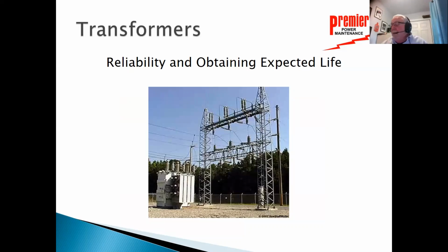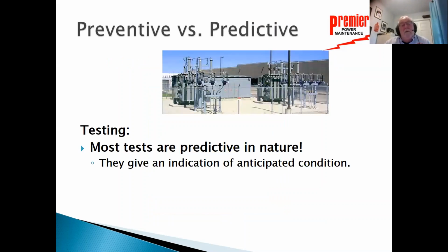So the second topic I want to talk about with regard to specific sections of reliability is the transformer. Let's talk about reliability and obtaining expected life out of a transformer. We get hired oftentimes to come out and the customer wants us to do preventive maintenance. Well, we need to discuss what the difference is between preventive maintenance and predictive maintenance. Almost all the tests that we do are predictive in nature. We're not preventing anything. We're just telling you the current status of this piece of equipment, okay? So most tests are predictive in nature, and they give you an indication of the anticipated condition. There's nothing preventive about that unless you take corrective actions after the testing is done. The testing itself is not preventive in nature.